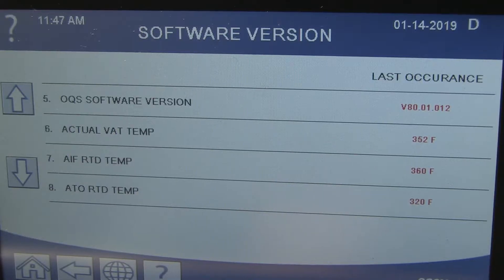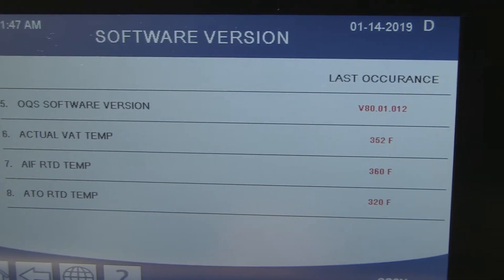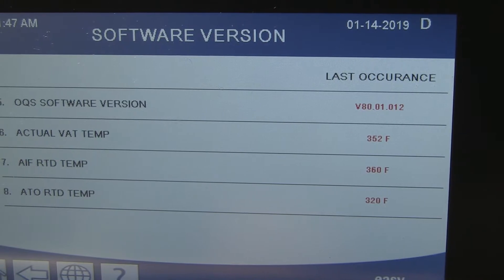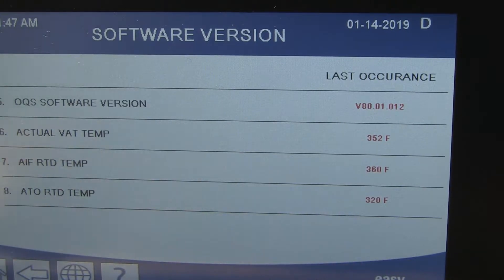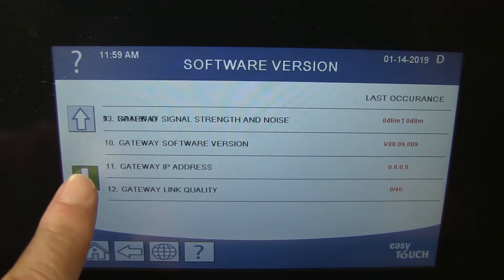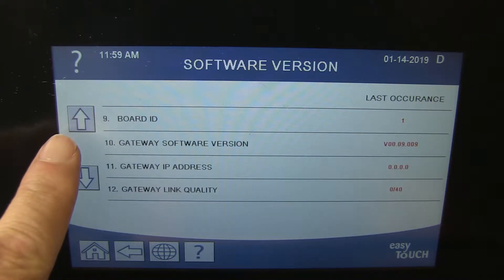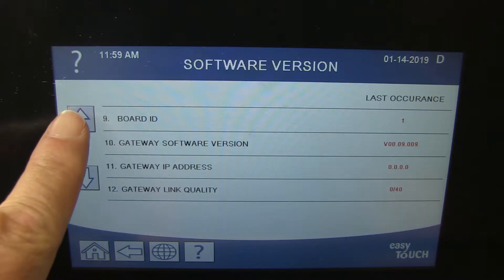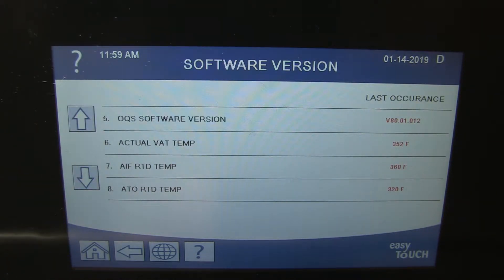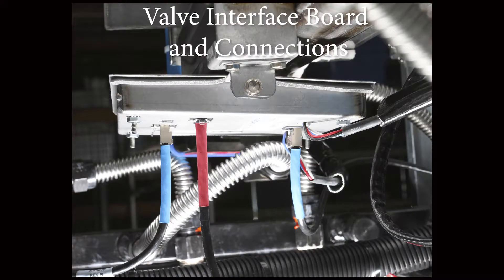You can also compare the temperature shown by the various probes — the values should be very close. The absence of a version number or a display of all zeros means the board is not visible on the network, but it doesn't mean the board has failed. More troubleshooting is necessary to get to the root cause.